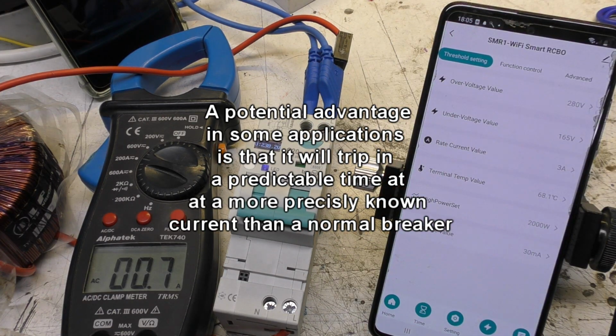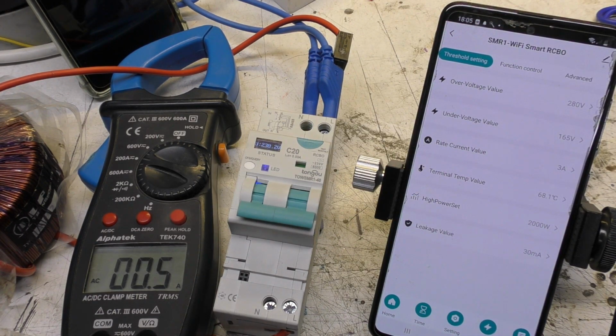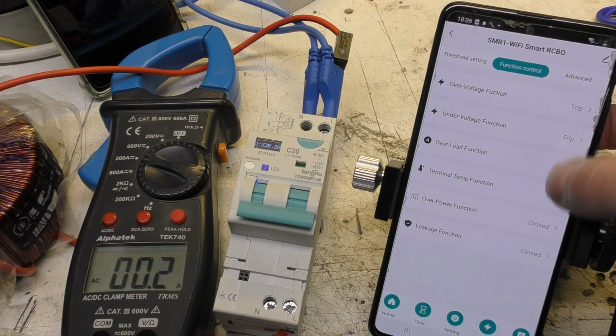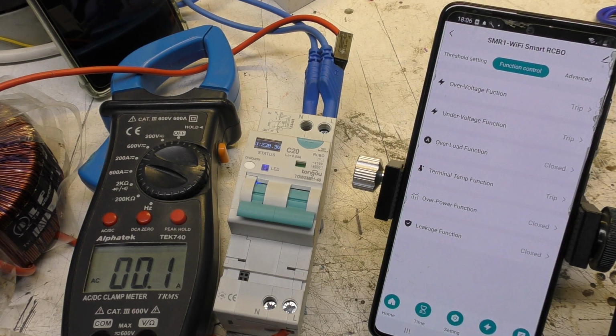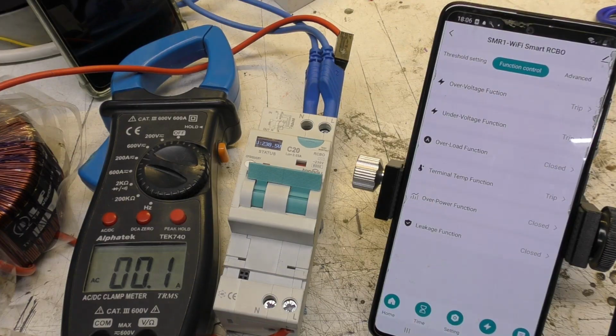It'll be interesting to see if there is any physical circuit breaker at all, like maybe a thermal one in here, but it does appear to be pretty much entirely software controlled. If we just turn the overload function off, we can quite happily stick sort of 50 amps through it, and it just sits there as if nothing was happening. So this is a thing that looks like a circuit breaker. This is very much not a circuit breaker at all.